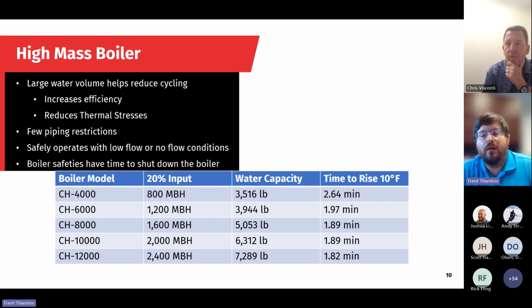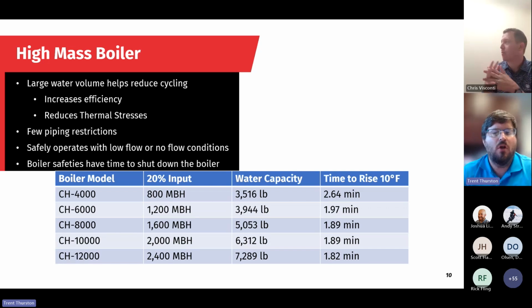One other feature that we like with the Cheyenne is that it is a high mass boiler. So when we say high mass, what we mean is high water volume. This high water volume changes temperature slower, particularly when there's a changing load. So when there's not a constant load throughout the entire day, the burner will modulate up and down to try to keep the temperature going out at the set point. Since we have a larger water volume, the burner has more time to modulate down when the load drops.